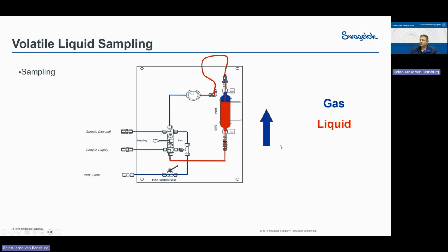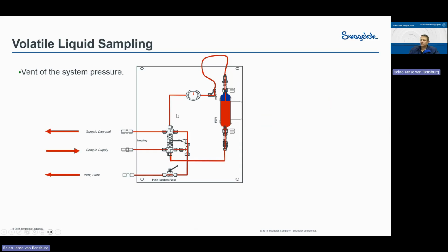Once it hits the outage tube on the inside of my cylinder, it basically gives me that blue vapor space. I can again see on my gauge that's now downstream of my cylinder again, that I've got pressure in my cylinder. We'll flow it through that cylinder. Again, same thing, close our valves on our cylinder to capture our sample in place. Then when we switch to the vent, same thing will happen.